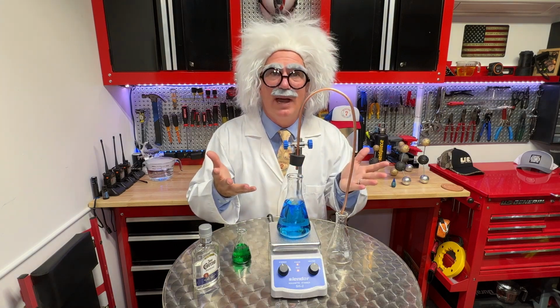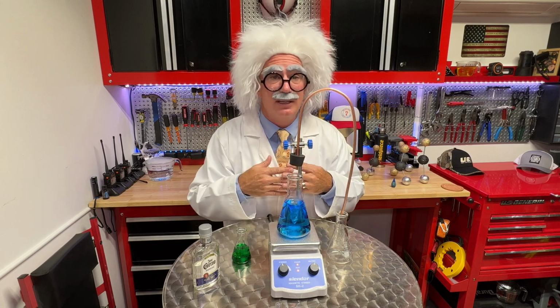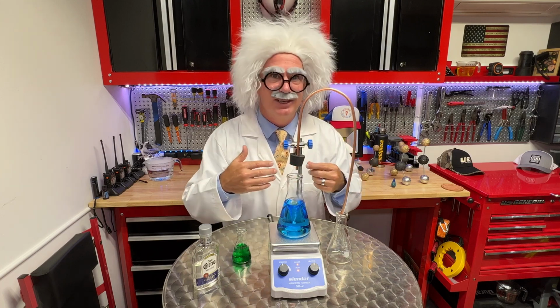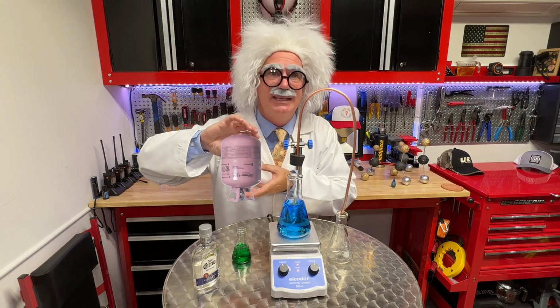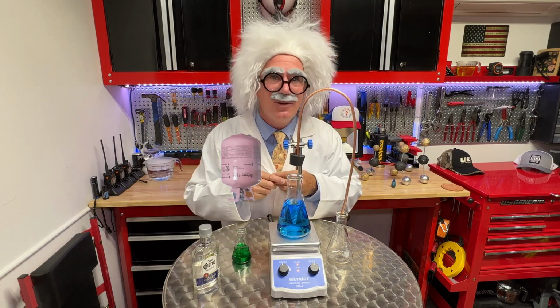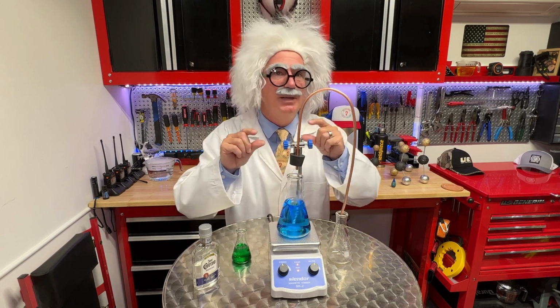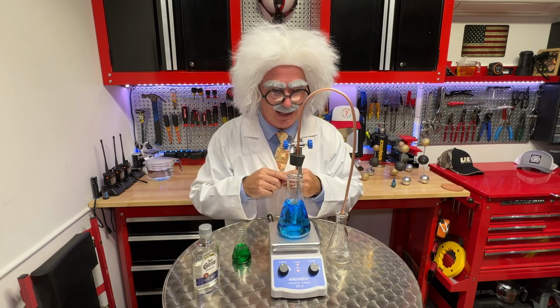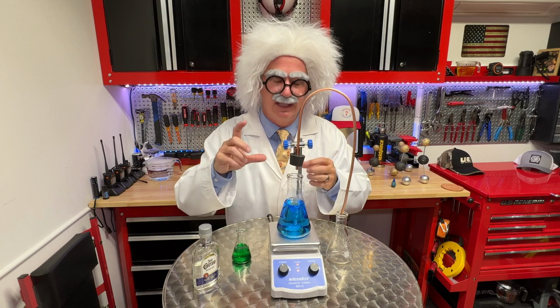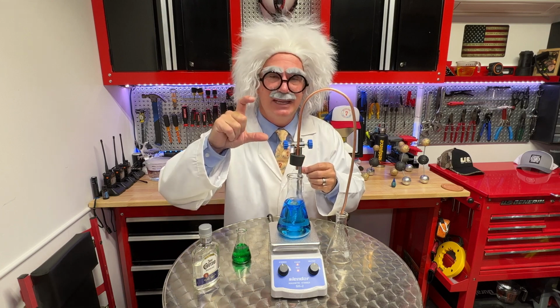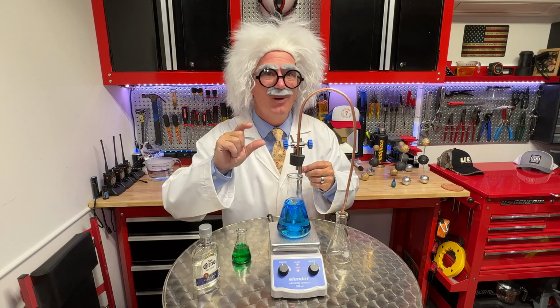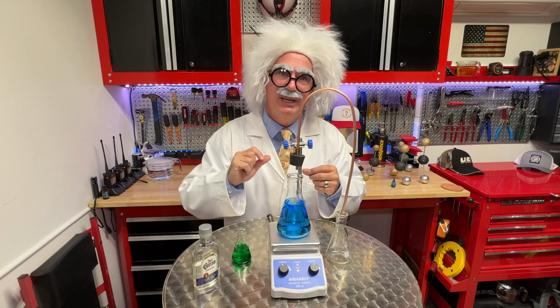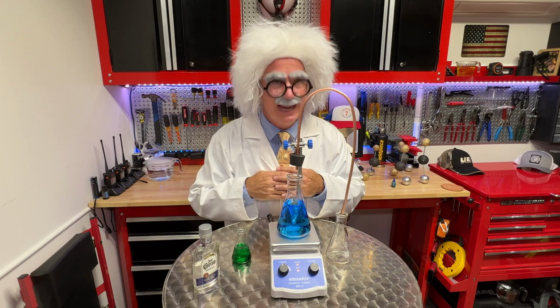So we just have to be aware that all of our 400 series refrigerants and 500 series refrigerants have that potential. That's why we charge them with the can upside down, so that we are only putting liquid into the system just in case they happen to be different inside of our tank. So learning that glide and fractionation happens in that window in between the two boiling points is very important when we're setting superheat and subcooling of our chemicals.